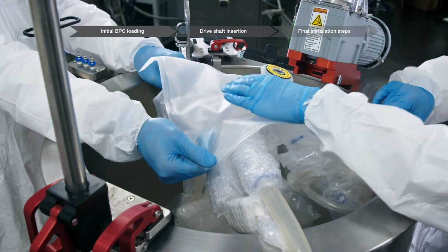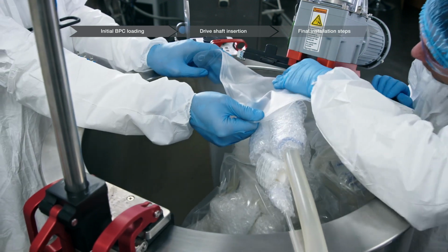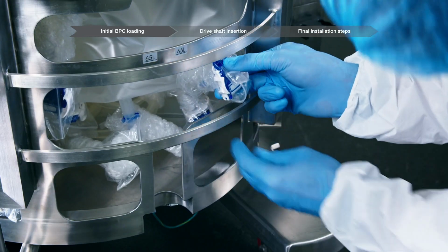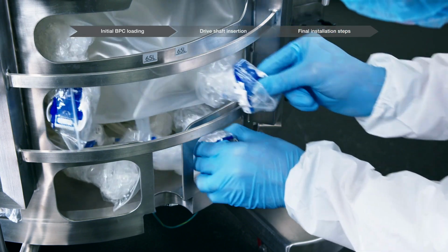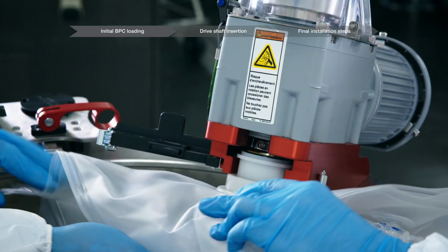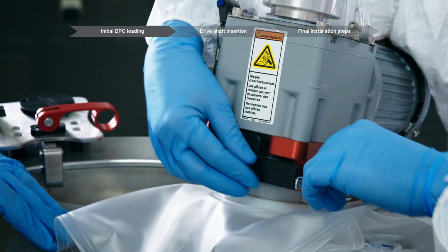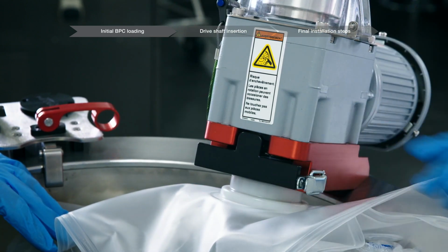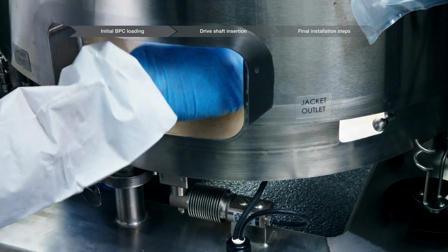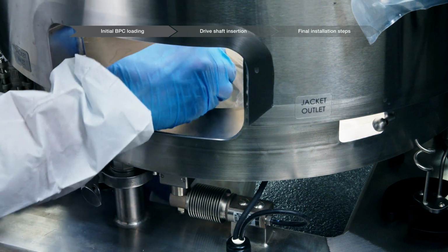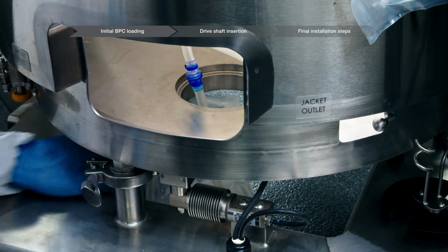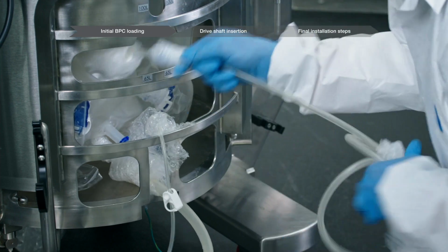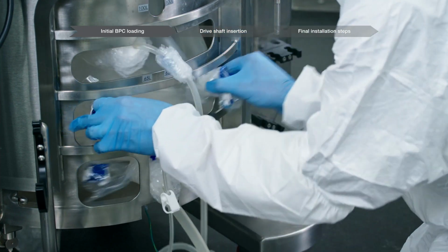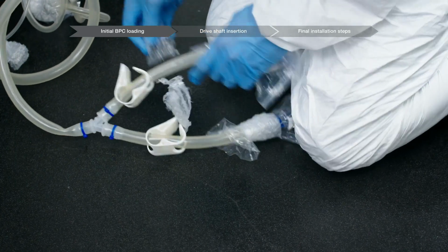Orient the BPC with the bearing port up and toward the motor drive, with the aseptic connector probe ports facing the bottom access cutout. Place the bearing port into the bearing port receiver, close the door, and close the clamp. Use the back access window to route the side and bottom ports through the opening in the outer support container. Route the sparge lines, bottom drain, and sampling lines through the appropriate openings and remove the bubble wrap.